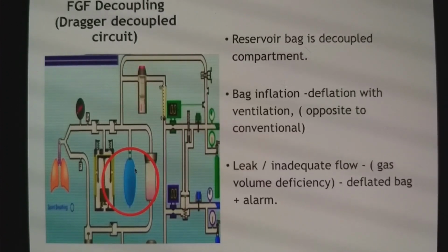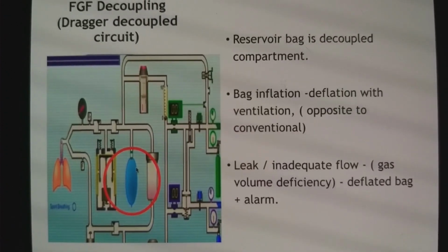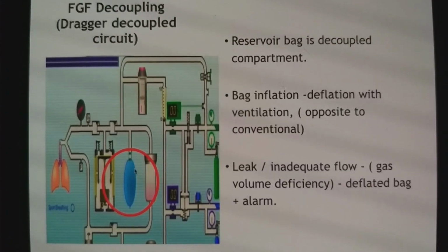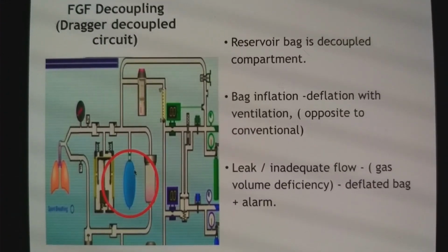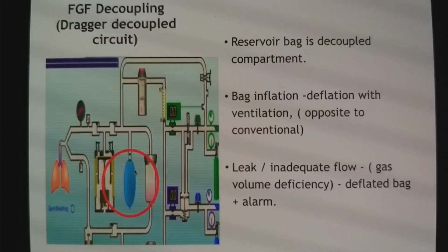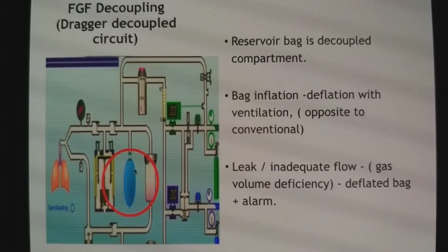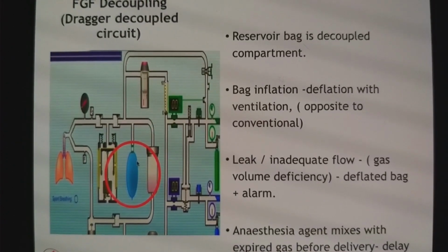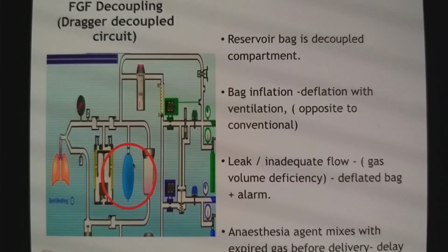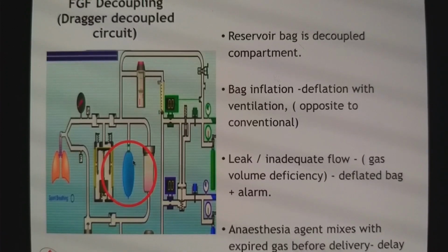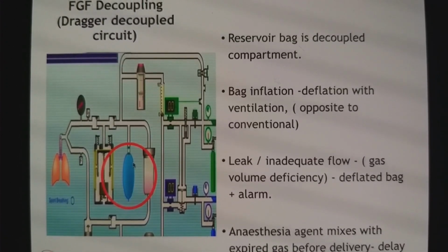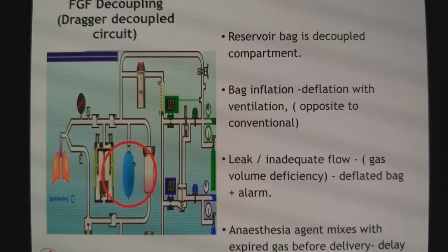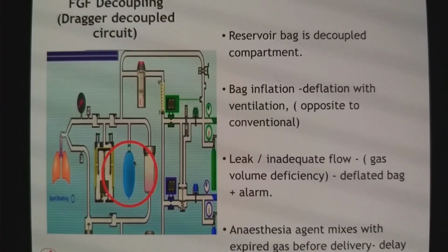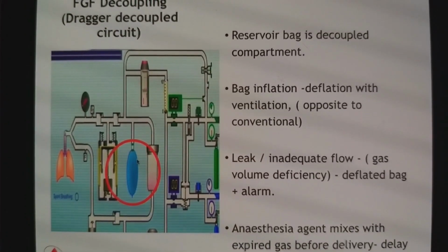And if there is a leak or if there is inadequate flow into your system, the bag will get deflated, and probably you will receive a message also that insufficient flow is there. So gas volume deficiency is identified by deflated bag plus alarm. Of course, there is a minor issue here: every time anesthetic gas comes to the reservoir, it mixes with the expiratory gas, and then it is delivered. So minuscule reduction or delay in the delivery of anesthetic agent can occur, but it can be easily compensated. So anesthesia agent mixes with expired gas before delivery, so there could be slight delay.